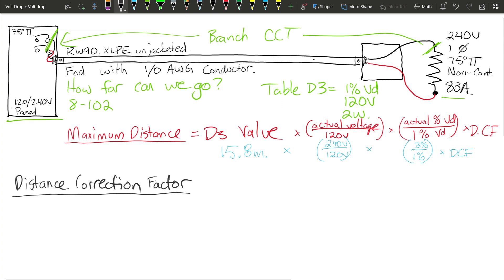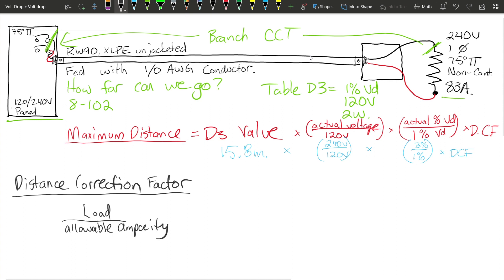We know the D3 value is 15.8 meters, but we might be able to go further because we're not fully loading this conductor. The Distance Correction Factor is calculated as: actual load divided by the allowable ampacity of the conductor. The allowable ampacity comes from Tables 1, 2, 3, or 4. In this example, with no more than three conductors in a conduit and no elevated ambient temperature above 30 degrees, we use Table 2.